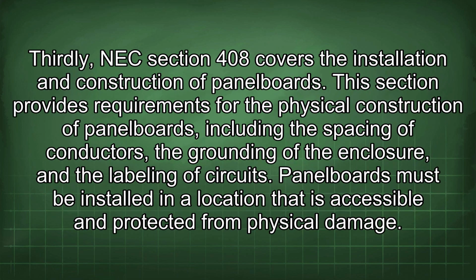Thirdly, NEC Section 408 covers the installation and construction of panel boards. This section provides requirements for the physical construction of panel boards, including the spacing of conductors, the grounding of the enclosure, and the labeling of circuits. Panel boards must be installed in a location that is accessible and protected from physical damage.